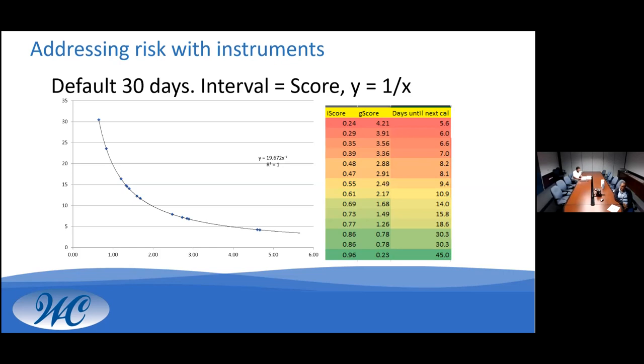Prior to calibrating, the buffers used to calibrate are read on the meter to measure sensor drift. So a meter checked against a pH buffer 7 with a reading of 6.8 would have a very poor score compared to a meter with a reading of 6.99. When the analyst submits the record, hundreds of lines of code run in the background that analyzes the current and prior calibration records for the instrument and updates its risk value. As found data is weighted heavier than as left data for risk calculations.